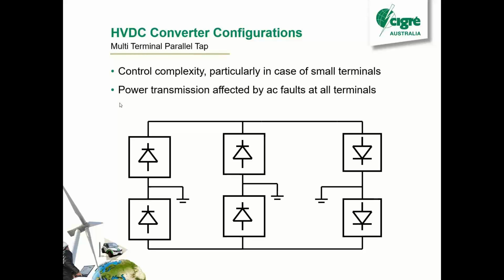So multi-terminal's been done a lot more with voltage source converters lately, and it actually works pretty good with voltage source converters. There have even been some hybrid systems where the sending end or the rectifier will be an LCC, and then they'll have multiple VSC taps coming off. And that seems to be working pretty well as well. So you take advantage of the low losses of LCC at your rectifier and invert with the VSCs. But yeah, included for completeness.